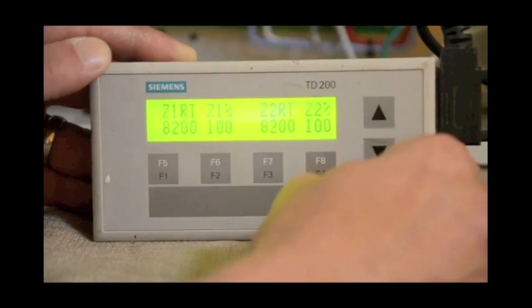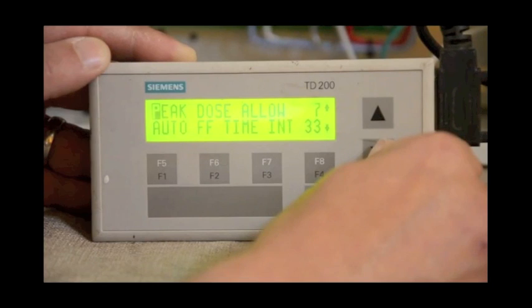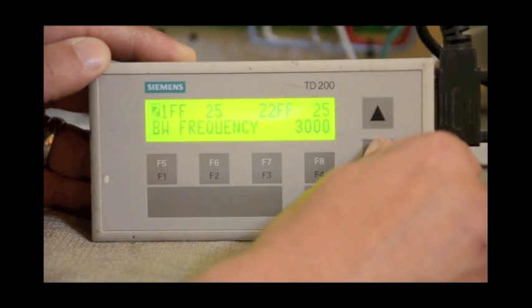The edit screen is used to change the percentages of pump run time for adjusting independent run times on different zones, your standard and peak rests for either a single or two zone system, and how many times you want to allow the system to dose in peak mode, and also change the field flush frequency to flush the fields more often.